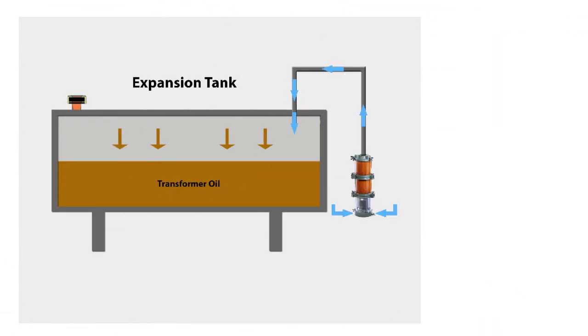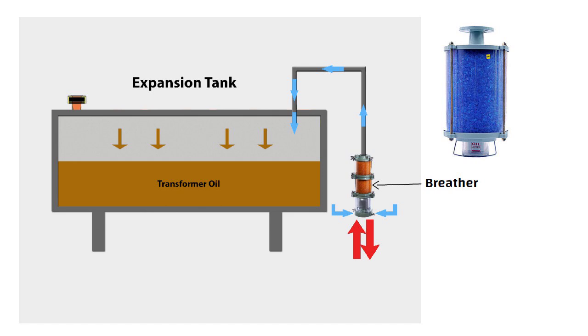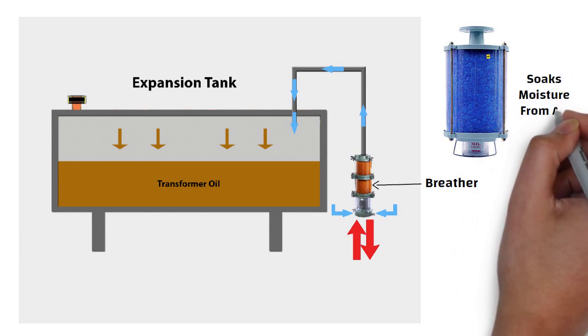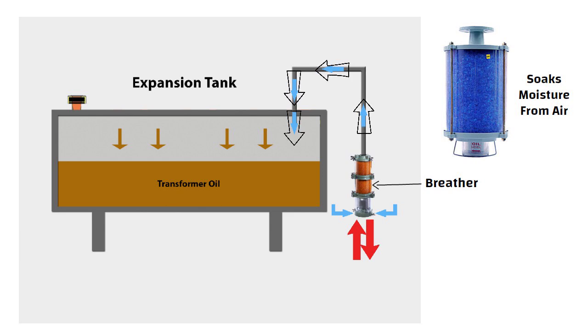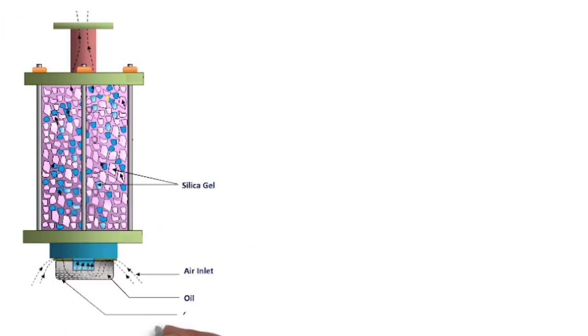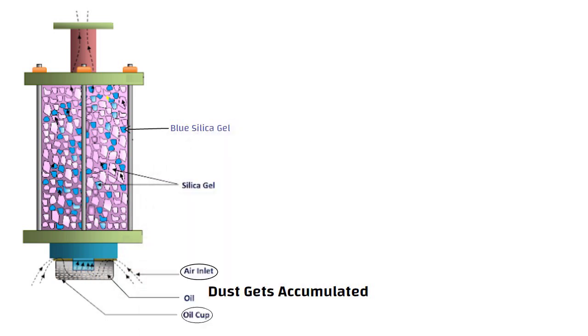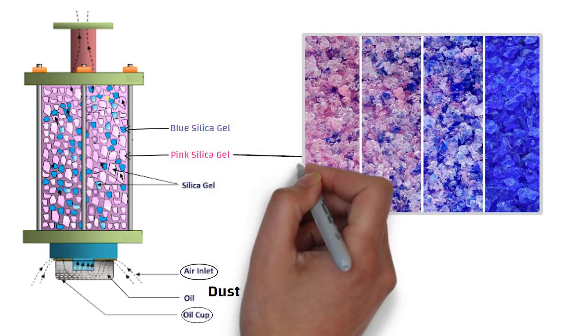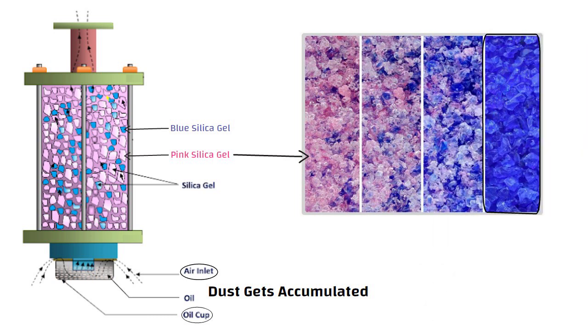To avoid this, you can see in this picture, the breather is attached to the end of the air pipe in such a way that the air enters and exits the conservator through it. This breather contains blue colored silica gel, which soaks moisture from the air and sends only pure air to the conservator tank. This is a detailed sketch of the breather. You can see the oil cup and air inlet at the bottom. Here the dust gets accumulated. The silica gel is blue in color. When it soaks moisture, it becomes pink colored. And when we remove moisture from this pink colored silica gel, then again it becomes blue and we can reuse it.